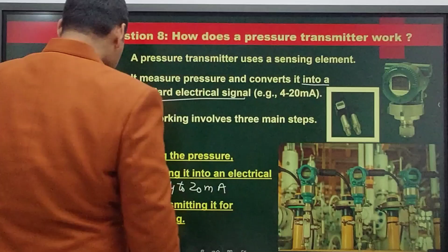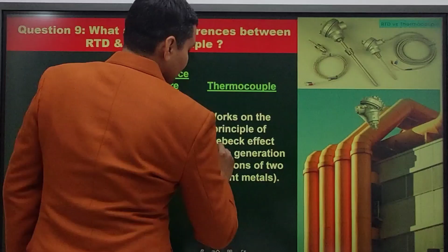Our next question is, what are the differences between RTD and thermocouple? This is a very important question and asked in many interviews. So we will discuss some important differences between RTD and thermocouple. Both are temperature sensors, both are used for temperature measurement. But what are the differences between these? So let's see. The first main difference is their working principle. RTD works on resistance change principle, but thermocouple works on Seebeck effect. When RTD is installed anywhere, its resistance will change according to temperature. But thermocouple works on Seebeck effect. Here voltage is generated at junctions of two different metals. Two different metals are used and two junctions are formed and a voltage is generated in thermocouple.